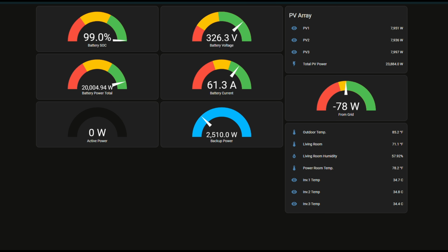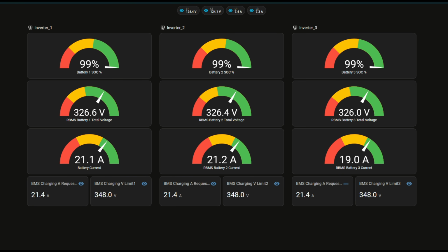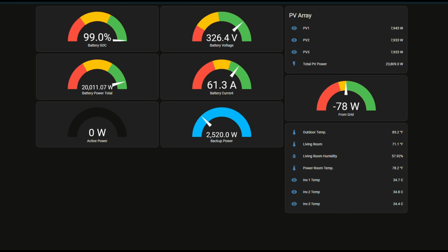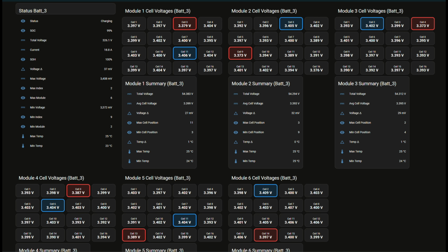When your home sometimes pulls 20 or 30 kilowatts, like mine does, running at a higher voltage means you can move the same amount of power with a lower current. That keeps cable sizes down, reduces power losses, and keeps wire costs in check. For example, instead of running expensive, heavy 4/0 wire everywhere, I can use off-the-shelf from Home Depot number 6 AWG wire for the entire system. That's only possible because the voltage is higher, so the current and therefore the heat and losses stay lower.